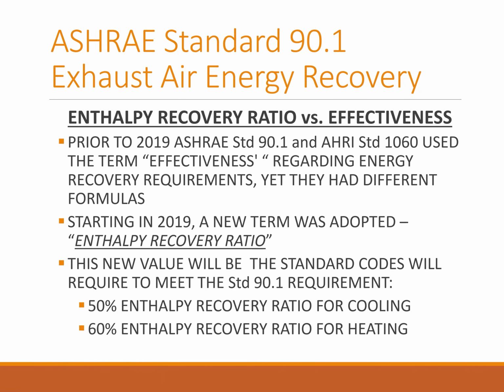Enthalpy recovery ratio versus effectiveness. As time has passed, the terminology for energy recovery has changed. For many years, effectiveness was the standard terminology. This has been replaced with enthalpy recovery ratio. One major reason for the change is that effectiveness formulas varied between ASHRAE and AHRI prior to 2019.